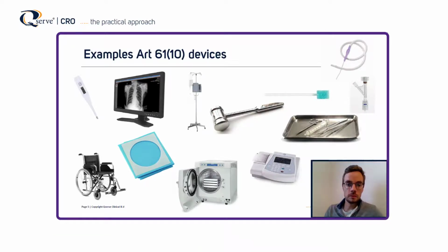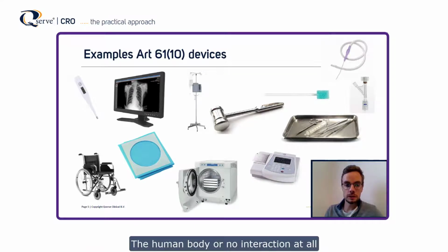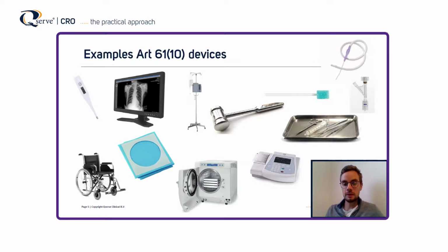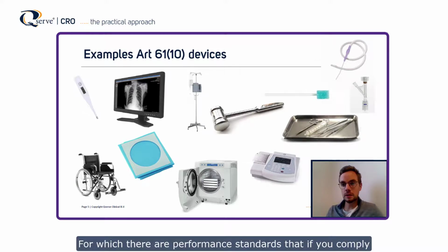And some, it's very obvious that there's almost no interaction with the human body or no interaction at all. For example, these medical displays that just show images that were collected with other medical devices. IV poles, a lot of accessories that come with these poles, some reusable surgical instruments, some disposable instruments, tubings, etc. Devices for sterilizing other devices, but also things like ECG amplifiers, for which there are performance standards that if you comply, you don't need to do any additional clinical data collection.